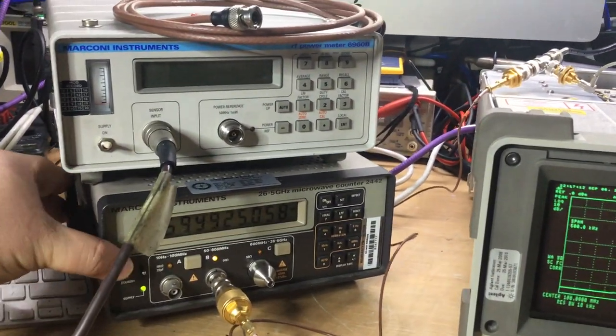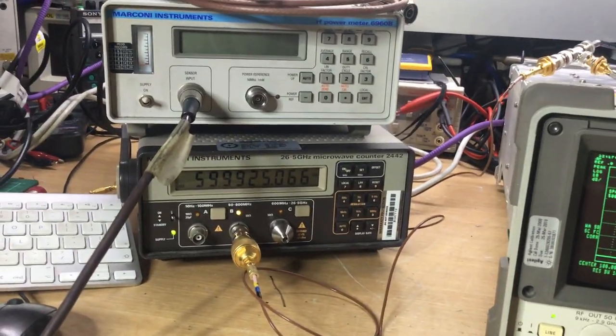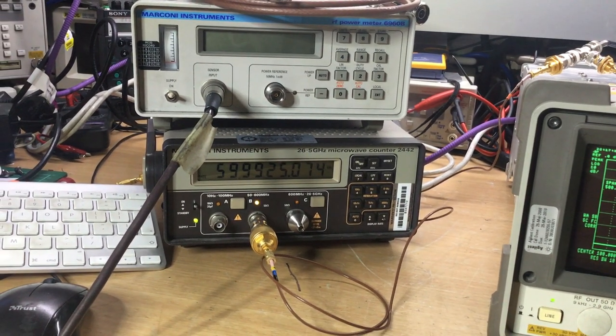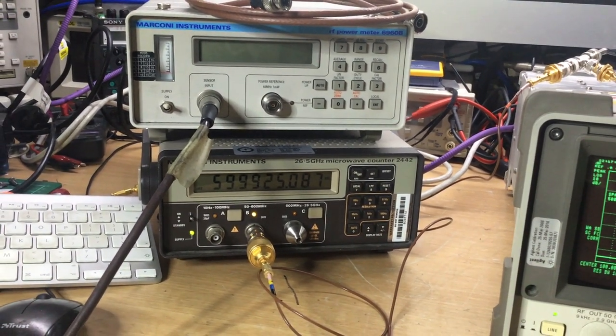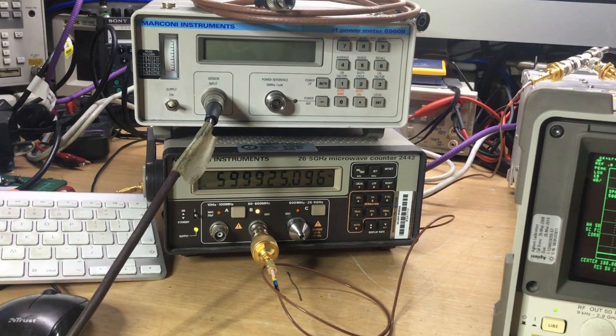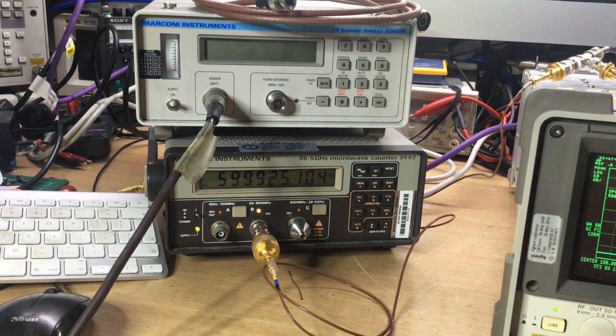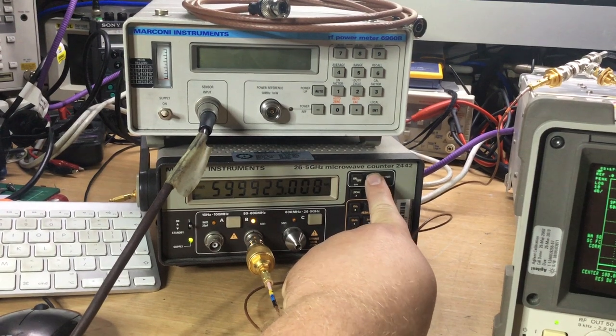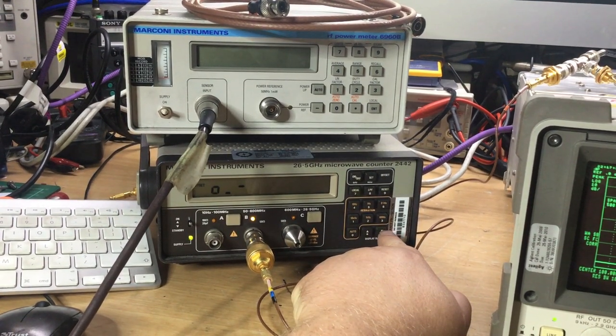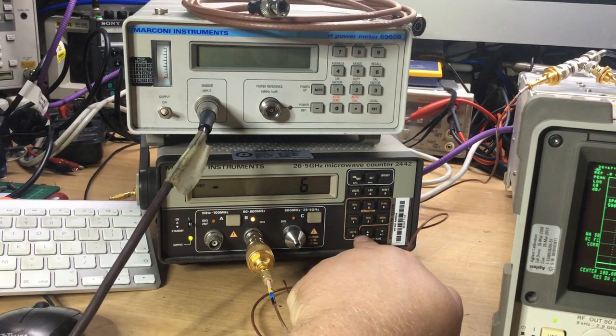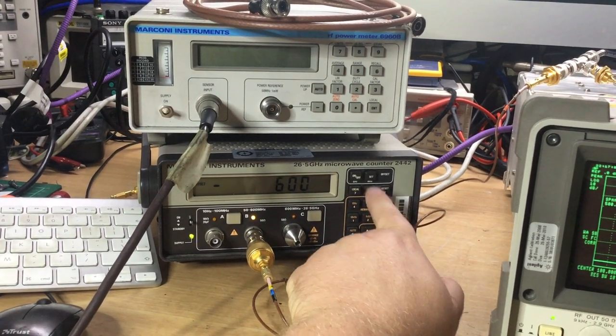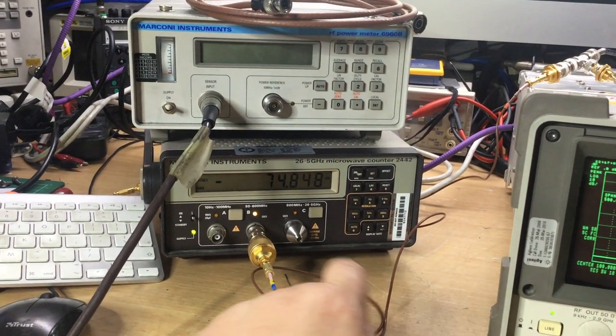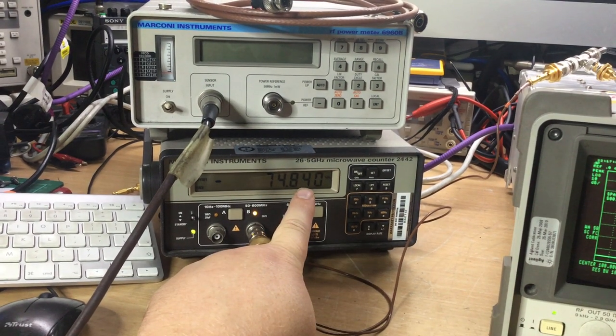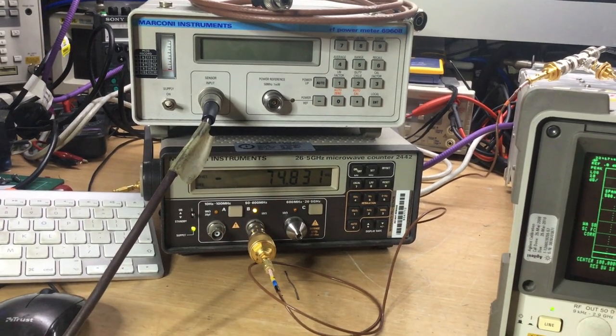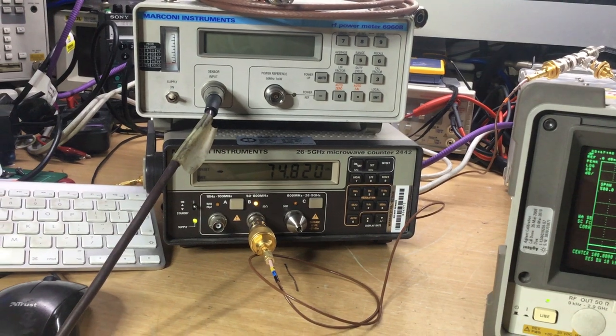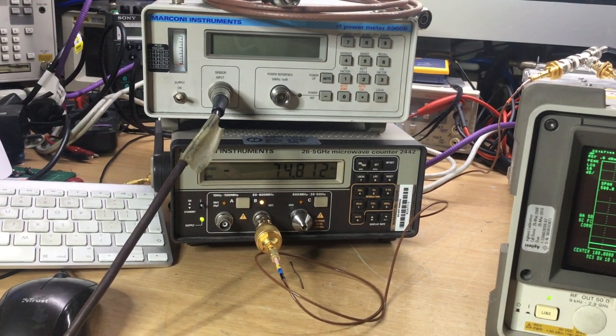Now, I've got this situation where I'm going to try and set the Marconi frequency counter to show us what the frequency error is of a 600 megahertz signal. So if I press the set key here and enter 600, 600 and then set, it's showing that we're 74.8 kilohertz off frequency. So that's roughly how far off frequency the 600 megahertz signal is.